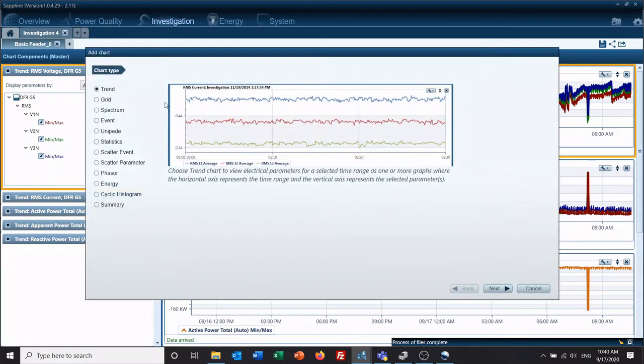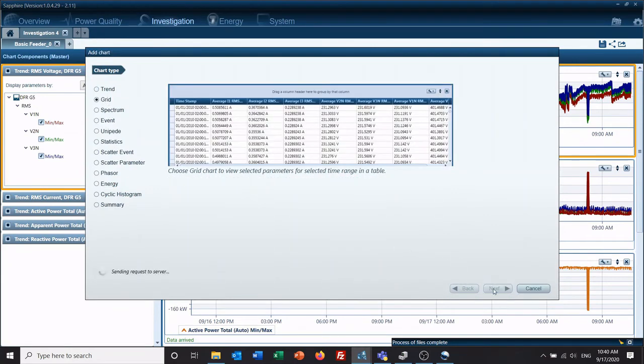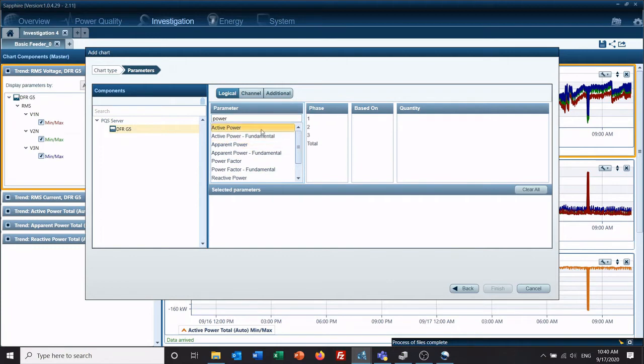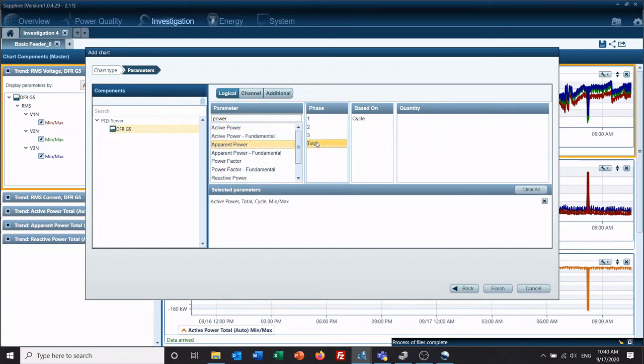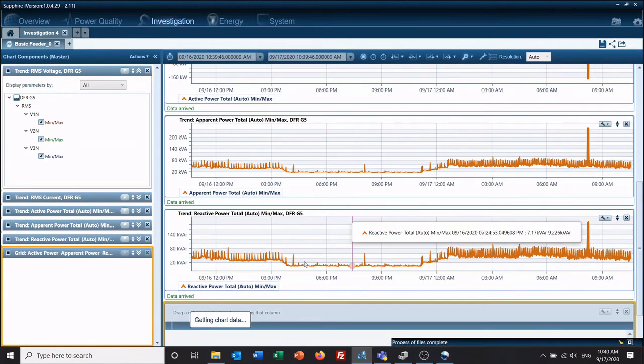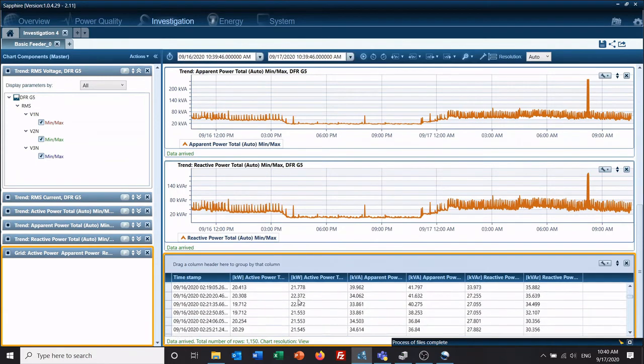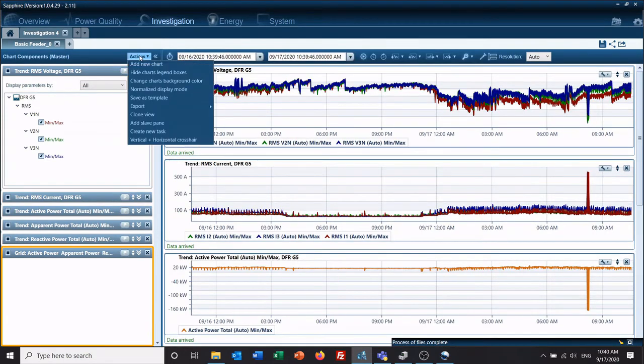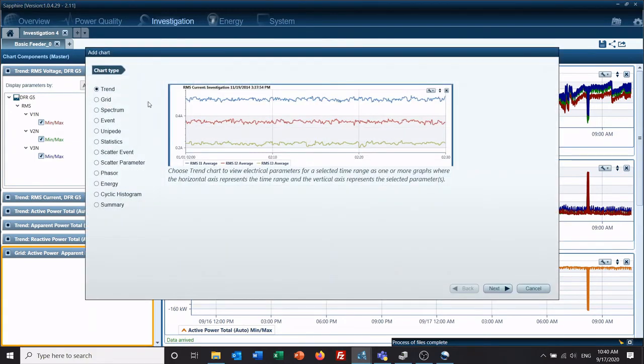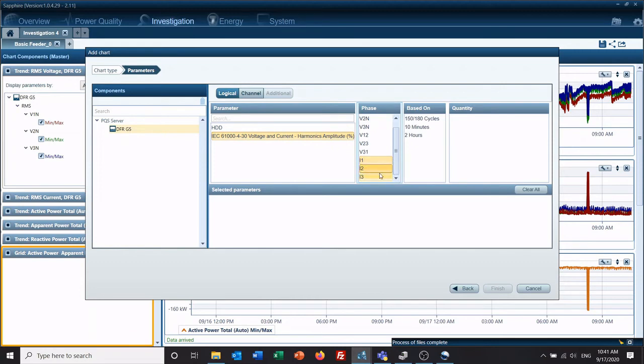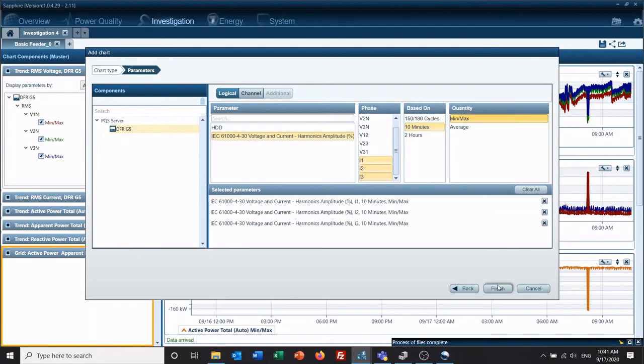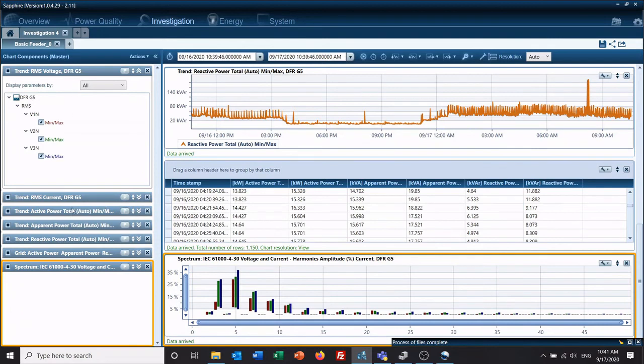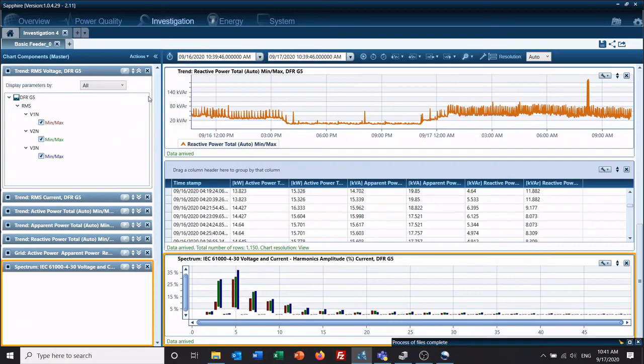But we're going to go ahead and add a grid with our powers. And so now we have this grid that has our powers. This is basically a spreadsheet of all this data. And let's go back in here and let's add spectrum. So we're going to look at current harmonics. I'll do it on a 10 minute aggregation. Finish. So now I have quite a bit more data here. Go to actions. Save as a template.